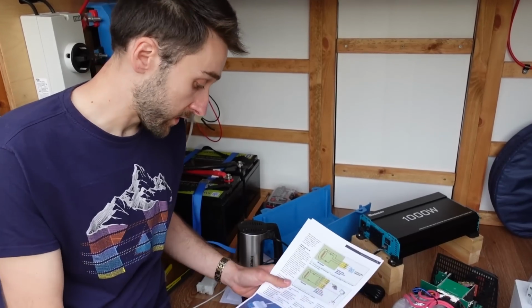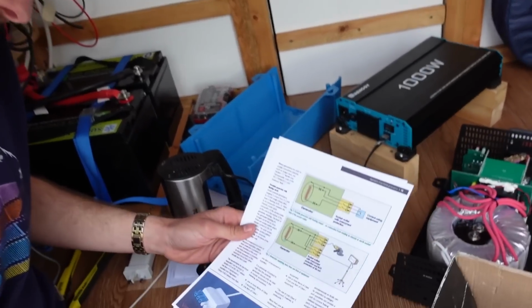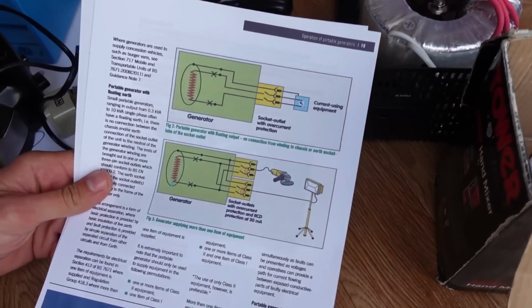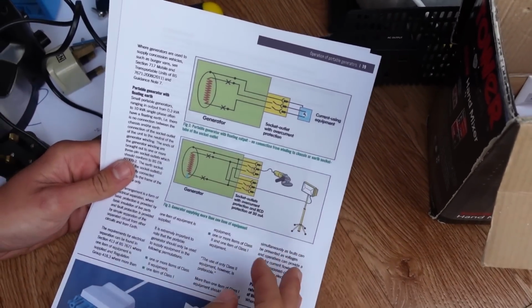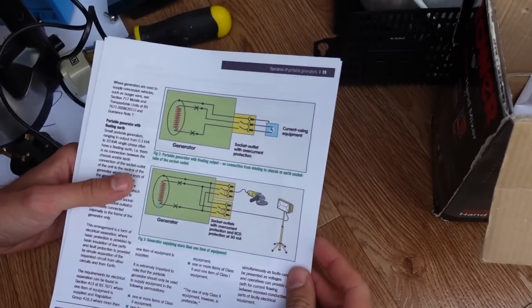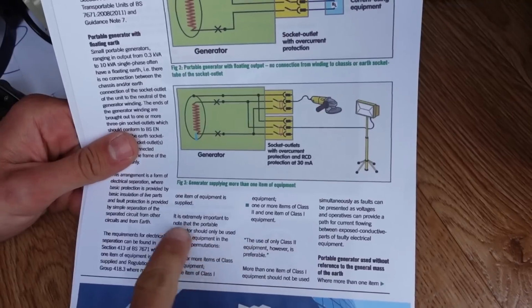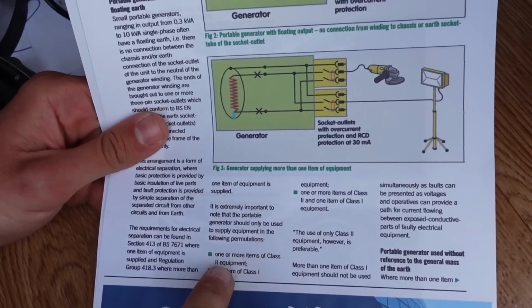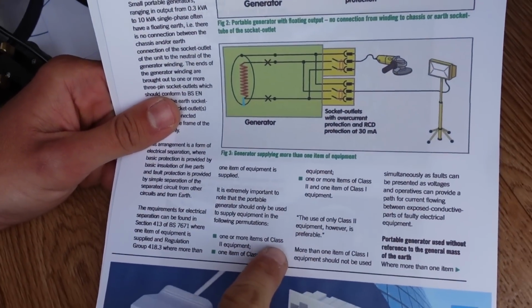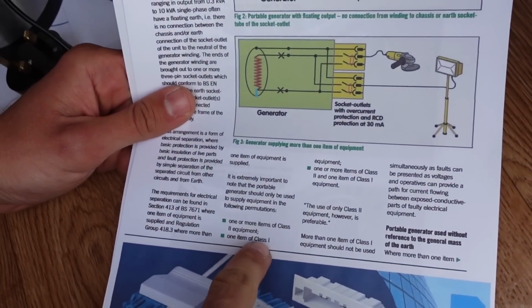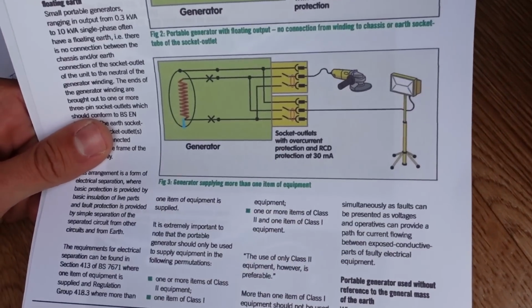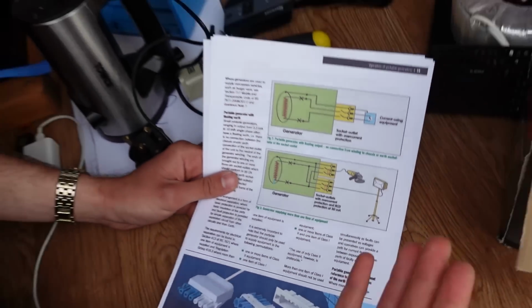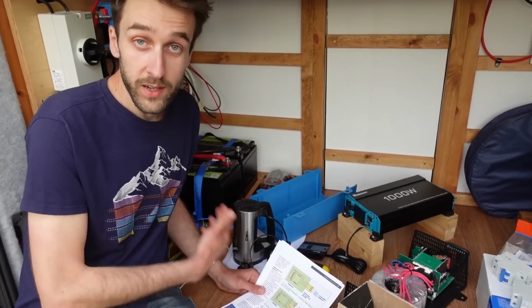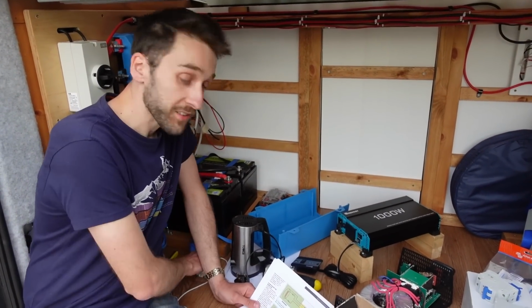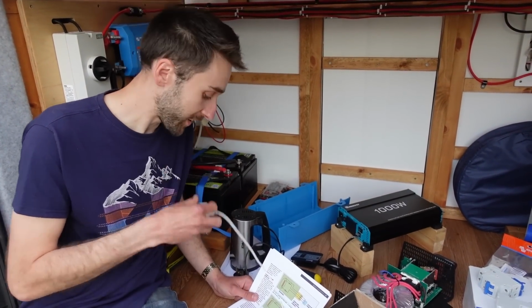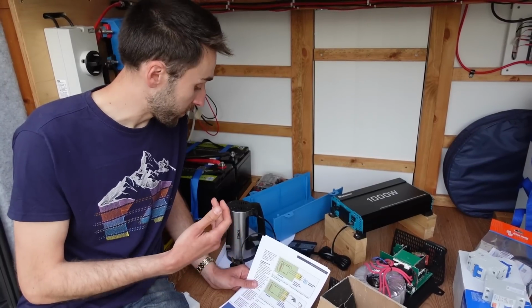We were looking at the British standard for this, BS 7671, which is for mobile generators, but the same principle applies for inverters. It says it's extremely important to note that you can only use it with one or more items of class 2 equipment, one item of class 1, or one or more items of class 2 and one of class 1. That means you can use as many class 2 devices as you like, like phone chargers, but only a single class 1 appliance.